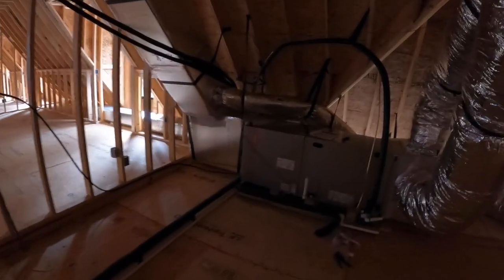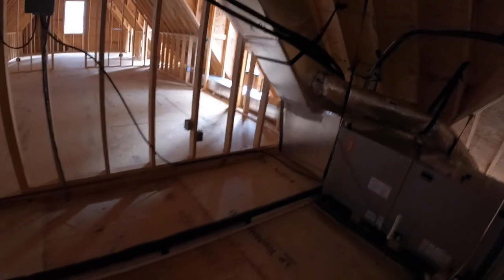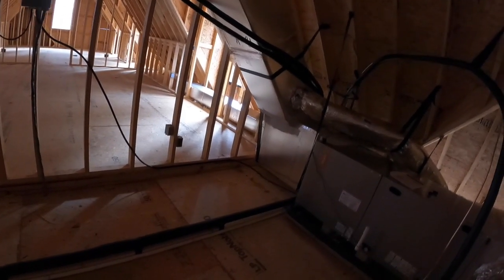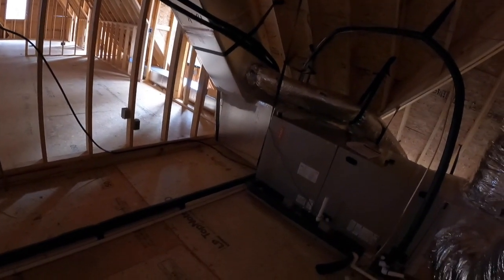Water should never get in this backup drain, but the municipality we're in requires that the pan be drained outside. The reason I don't like that is because where this comes out, I can fit my index finger all the way under this outlet - you can't really see it well, but my finger goes all the way under there. So this pan would have to get about an inch of water in it before water would even drain outside, and then the homeowner or business owner would have to notice water coming out of that pipe and understand that's a problem before we even get a phone call.